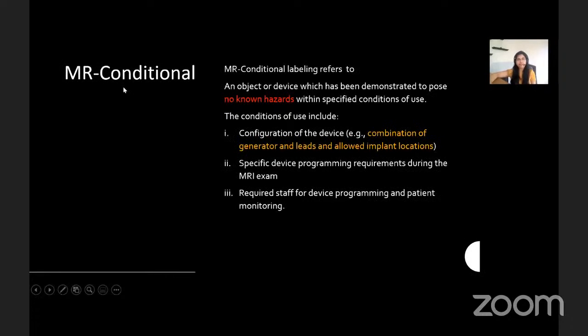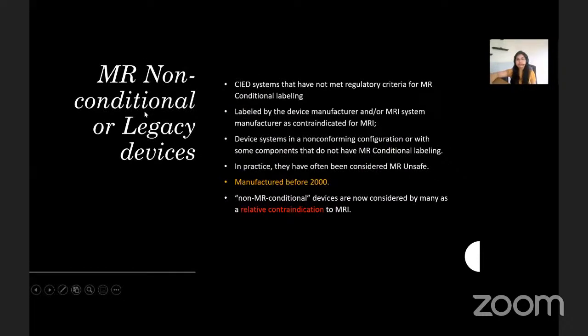When a device is labeled MR conditional, it means that such a device poses no known hazards within specified conditions of use. These conditions include a conditional labeling for the combination of the generator and leads, allowed implant locations, specified device programming requirements, and availability of required trained staff for device programming and patient monitoring. A non-MR conditional device is a system that has not met the regulatory criteria for MR conditional labeling — pertaining to the entire device or only some of its components. They are considered MR unsafe and have an older manufacturing date, usually before the year 2000. These legacy devices are now considered a relative contraindication for MRI.